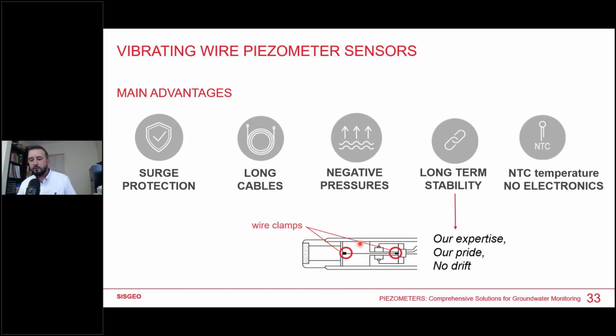Here, on the principle, you can see the diaphragm, and here the seat, let's say the main body, and here the electrocoil. These 2 points are the clamping. Remember, the wire is clamped and put into tension. The expertise that the clamps are made in such a way that they don't drift in time is our pride. It's the main factor that makes our sensor better than the others.